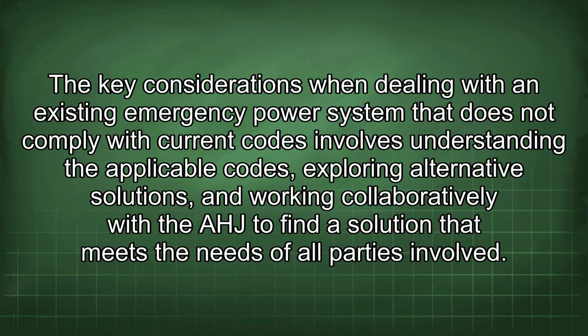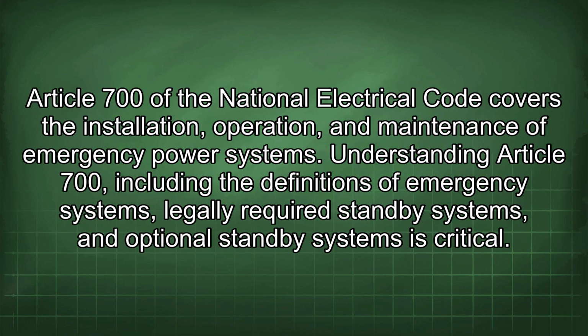The key considerations when dealing with an existing emergency power system that does not comply with current codes involve understanding the applicable codes, exploring alternative solutions, and working collaboratively with the AHJ to find a solution that meets the needs of all parties involved. Article 700 of the National Electrical Code covers the installation, operation, and maintenance of emergency power systems. Understanding Article 700, including the definitions of emergency systems, legally required standby systems, and optional standby systems, is critical.